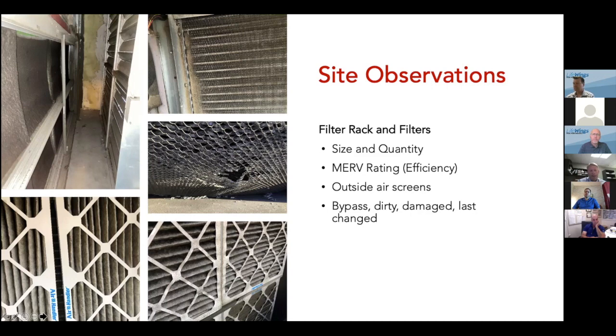So any air that passes around the filters goes directly into the coil. If it's not caught by the coil, it goes into the ductwork. If it's not caught in the ductwork, it goes into the airstream and out into the classrooms. In the upper right photo, you can see how much dirt and debris has collected on the coil. Just on the left-hand side of the coil, you can see an inch or two that is totally plugged. So all that dirt that's bypassing the filters is getting caught in the coil or downstream.